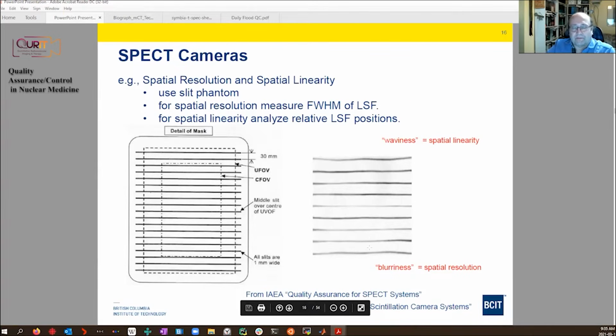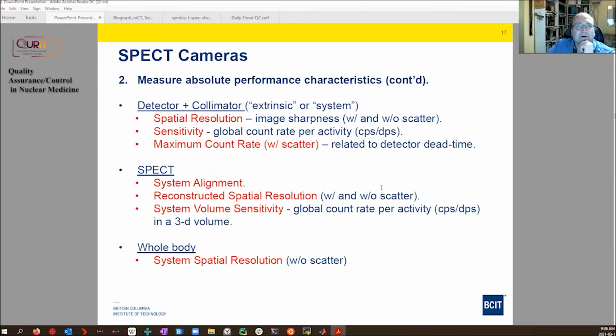And the way you actually measure the spatial resolution is if you take a profile through these line sources, or these lines on the image, you get what we call a line spread function, and you can measure the resolution by measuring how wide that is. Again, if we had more time, I'd go into the details of that measurement. So these are 2 of the measurements.